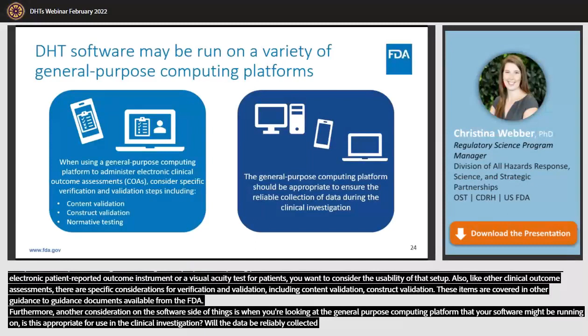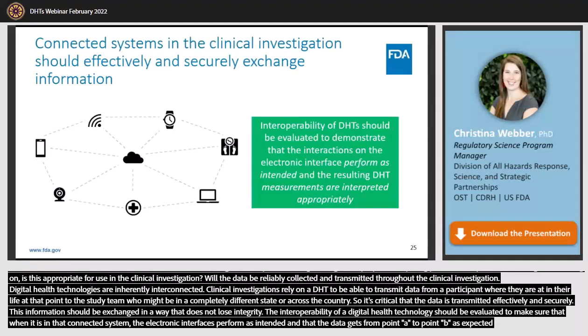Digital health technologies are inherently interconnected. Clinical investigations rely on a DHT to be able to transmit data from a participant where they are at in their life at that point to the study team who might be in a completely different state or across the country. So it's critical that the data is transmitted effectively and securely. This information should be exchanged in a way that does not lose integrity. The interoperability of a digital health technology should be evaluated to make sure that when it is in that connected system, the electronic interfaces perform as intended and that the data gets from point A to point B as expected, so that when the analysis is done, the measurements may be interpreted appropriately.